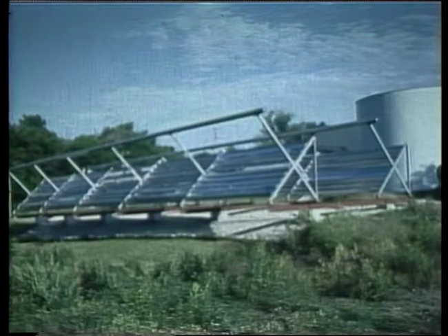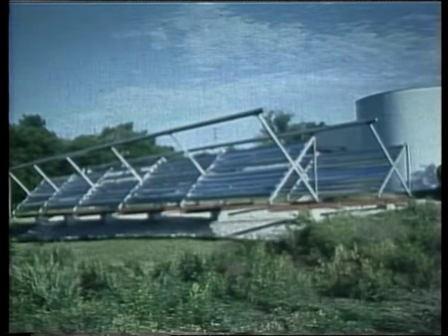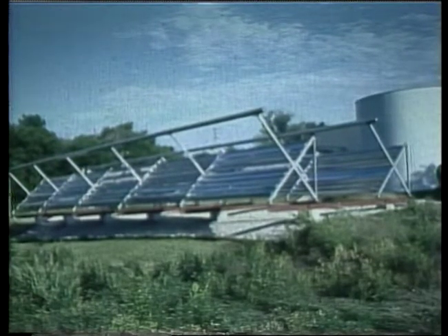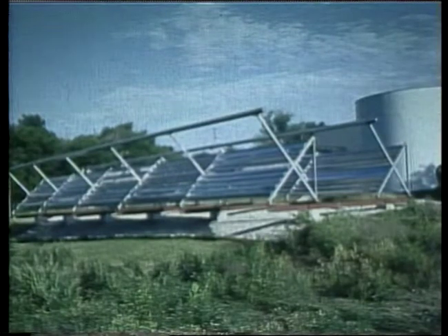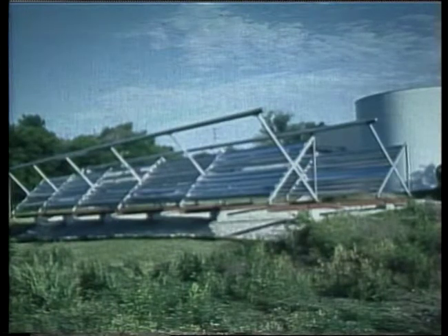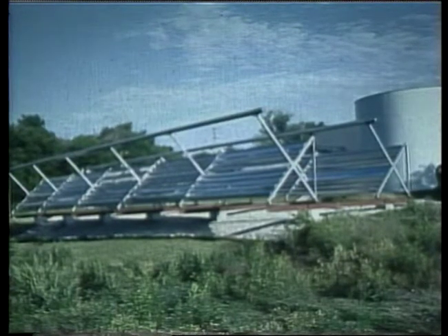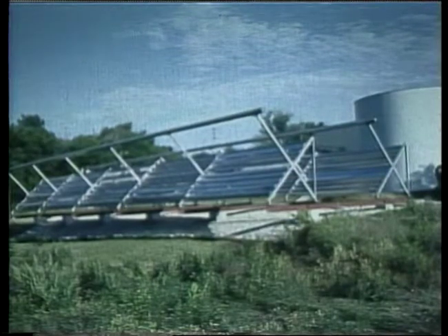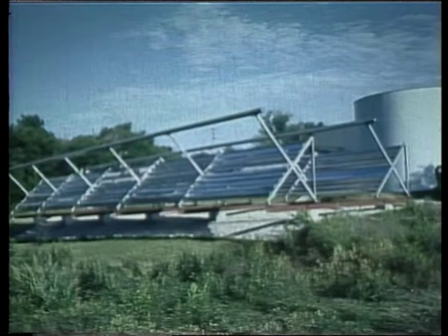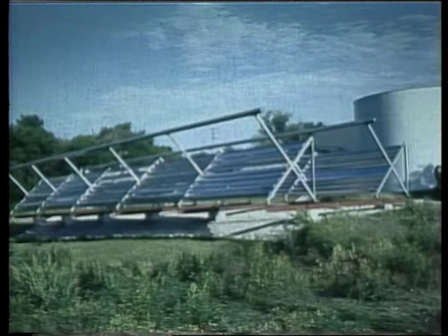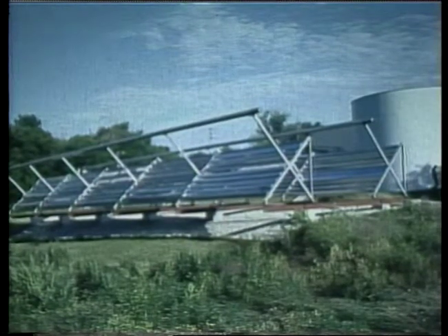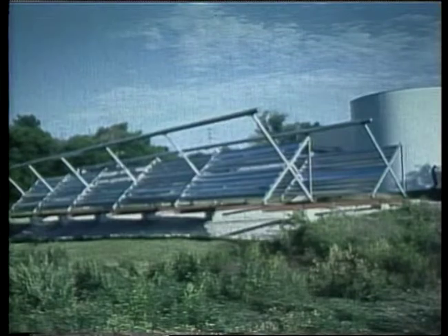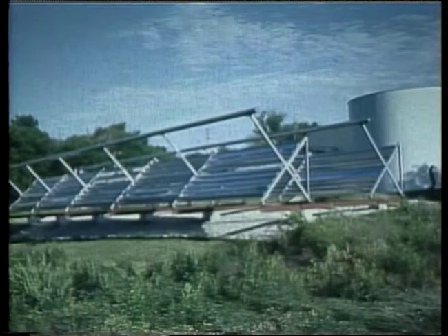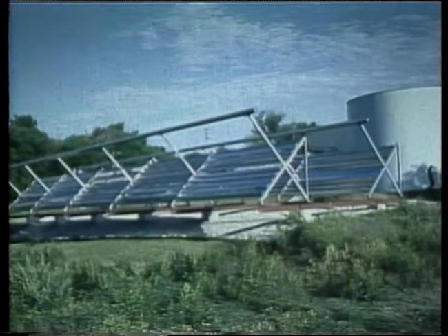And if your building is heated with high temperature steam, the flat plate is not going to do it. It loses energy according with its area, you see. So if you compress that area down and focus the energy on that area, you lose less energy and therefore you get higher temperatures. And this is a focusing collector here of that type, used to generate steam actually. So the collectors actually focus on the sun and concentrate the energy on a small area, and therefore the loss is small, relatively.